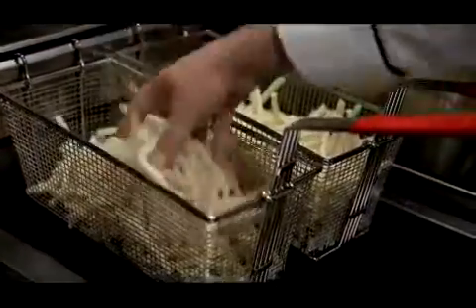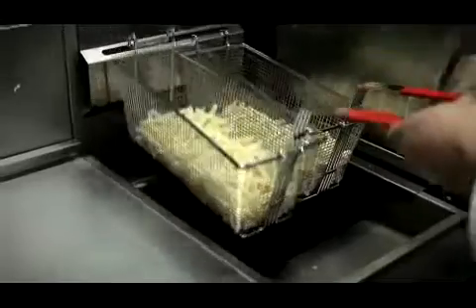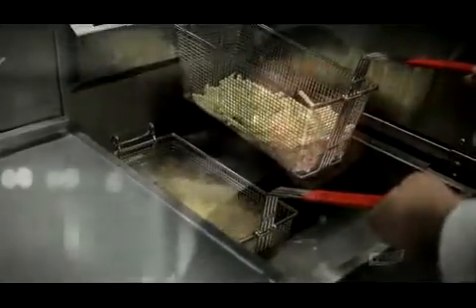The more times you move that heat back and forth through the oil, the more opportunity it has for that heat to absorb into the oil, so that you have less heat exiting the fryer — thus lowering flue stack temperatures.